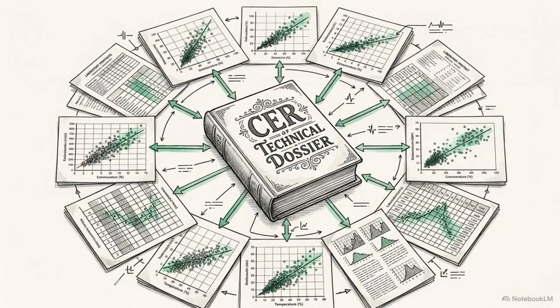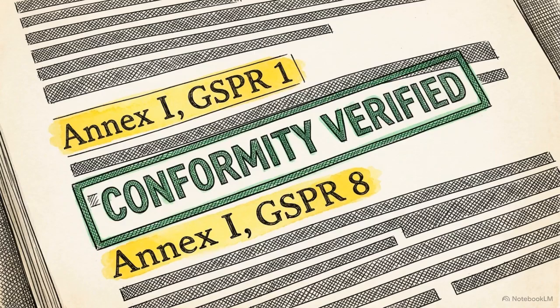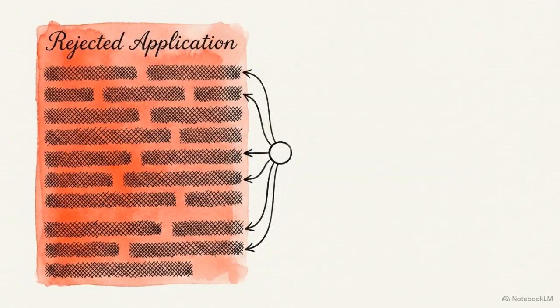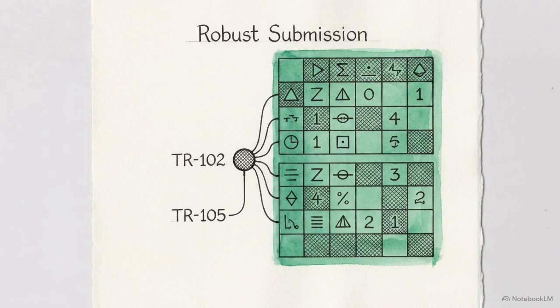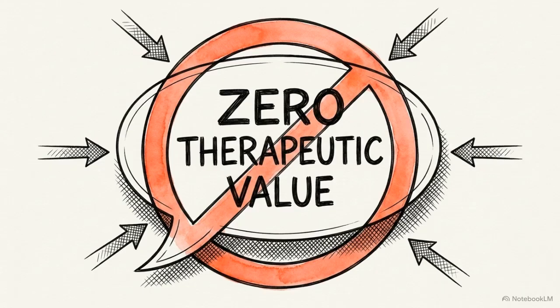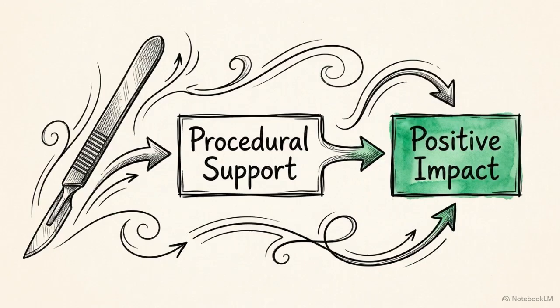With the evidence gathered, you synthesize the non-clinical data into the clinical evaluation report. This section must conclusively prove conformity to General Safety and Performance Requirements 1 and 8. This comparison shows how notified bodies evaluate these documents. The deficient submission on the left simply reiterates the legal text of the MDR. The detailed matrix on the right references specific bench test IDs mapped directly to the required state-of-the-art parameters. Do not attempt to bypass clinical requirements by claiming the device has no clinical benefit. Every medical device must prove at least an indirect benefit, such as facilitating a surgical procedure, to pass the mandatory benefit-risk analysis.